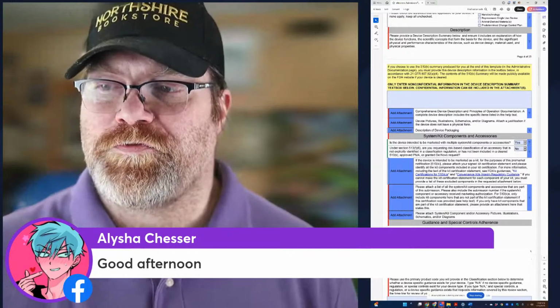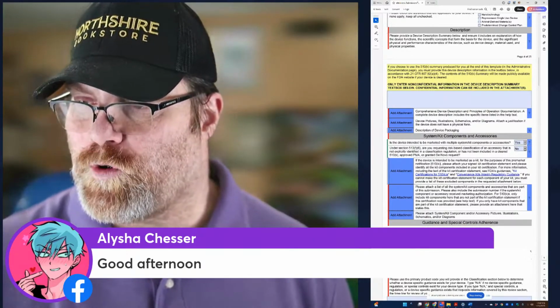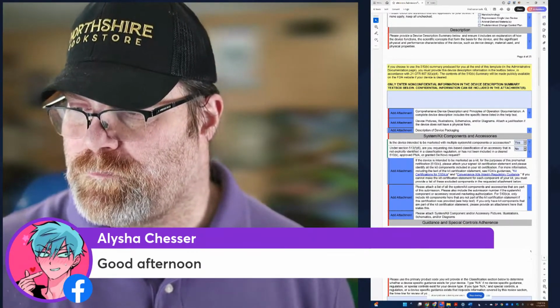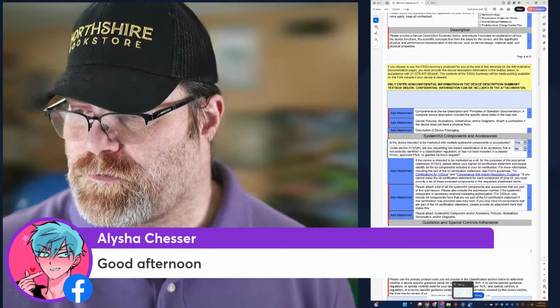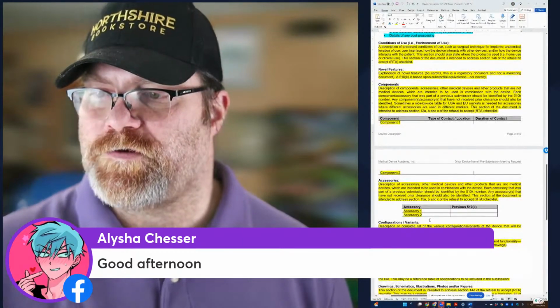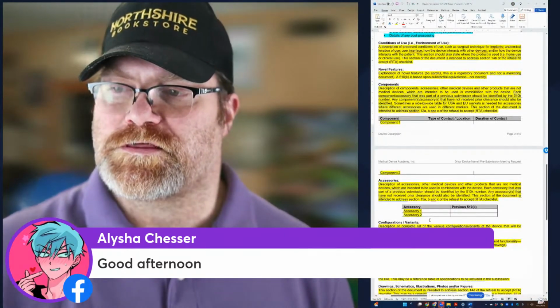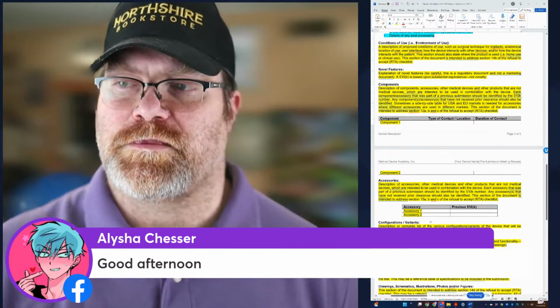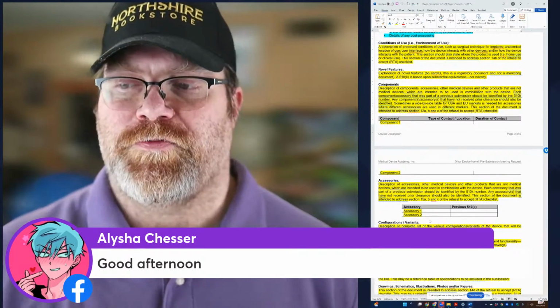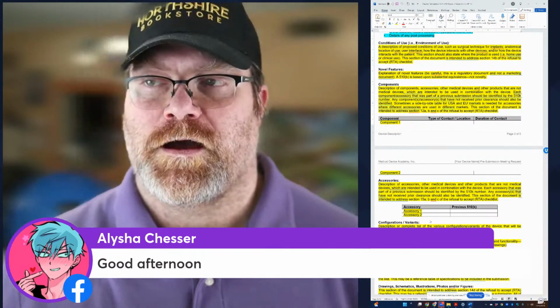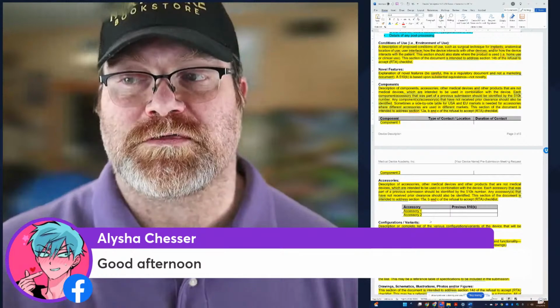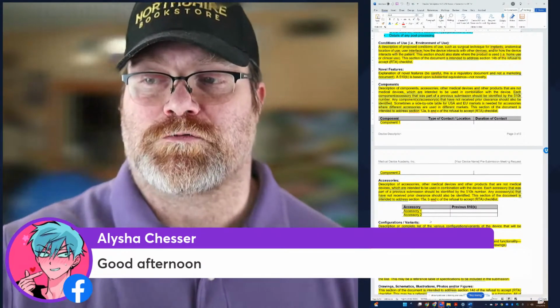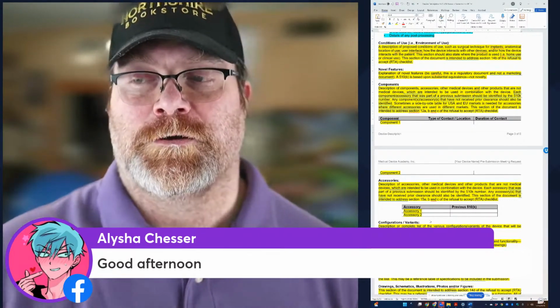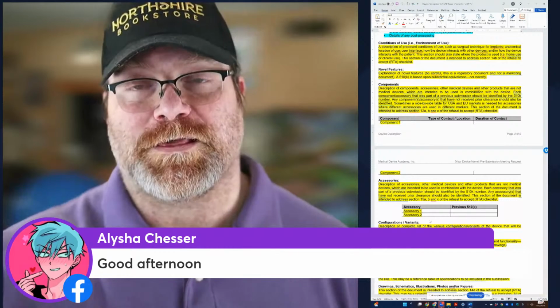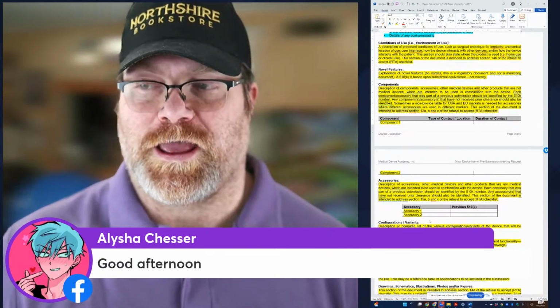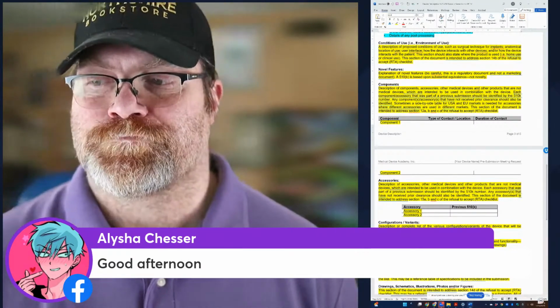So that's one of the things that you can take out, and I'll show you where you would take that out of our device description template. So here's the device description template. Those accessories and components that are in the middle of the page around the page break, that's what you could remove. You would still want to include your components, the functional components, but you can remove the accessories part because those accessories could be listed in the kit and you wouldn't have to list them in both places.